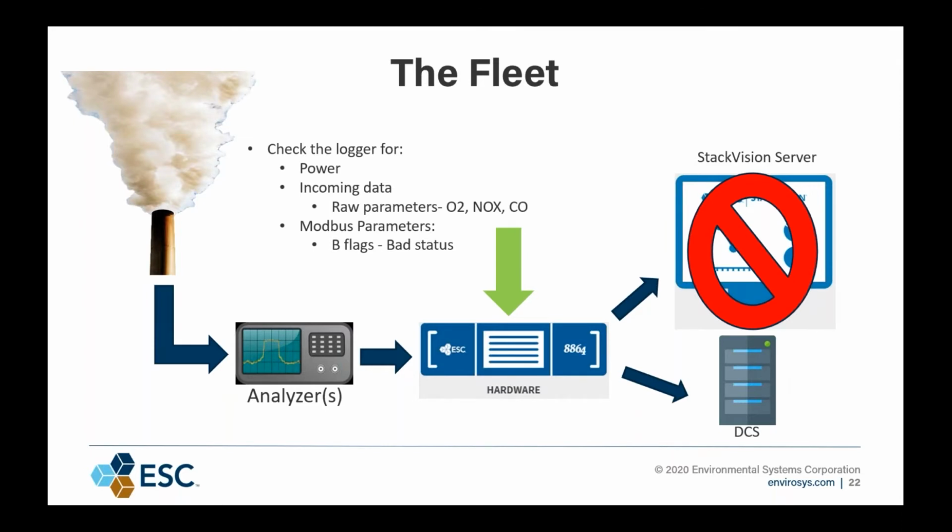For this, you're going to need to call support, and depending on the time of day, we could possibly get a logger to you by the next day, but I believe 3 o'clock is the cutoff time from which we can send out another logger after processing this. If you are a technician and you're unfamiliar with the 8864, which most are, the first place you might usually check when your data is missing may be your analyzer. There's nothing wrong with that, but you could possibly just check your data logger and know that your analyzer and your 8864 are bringing in data.